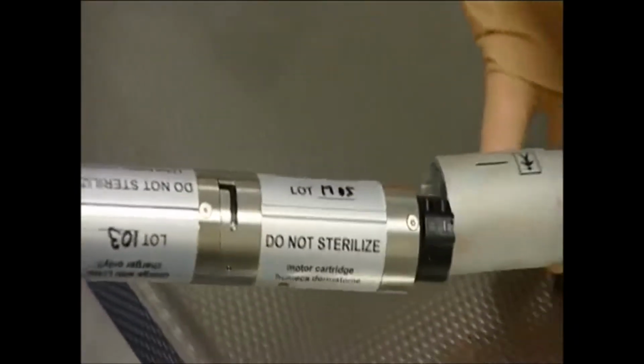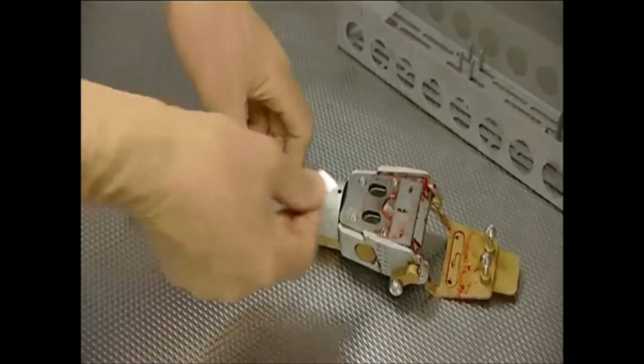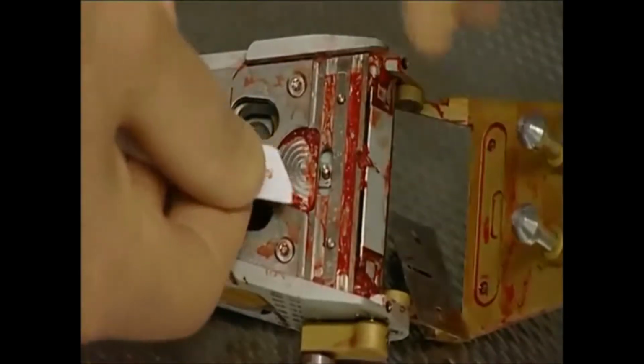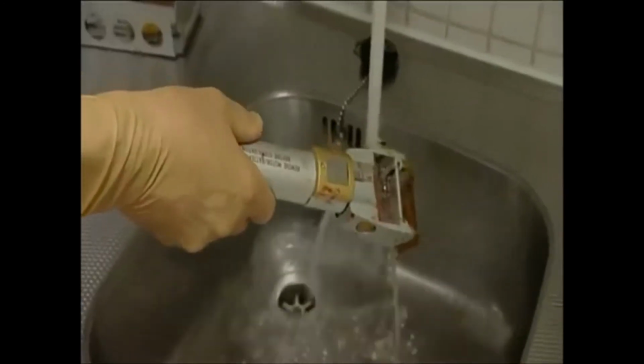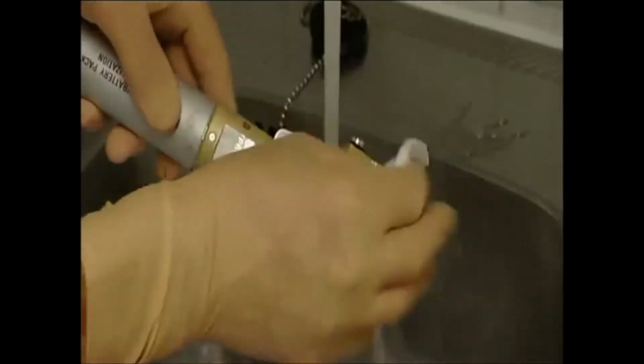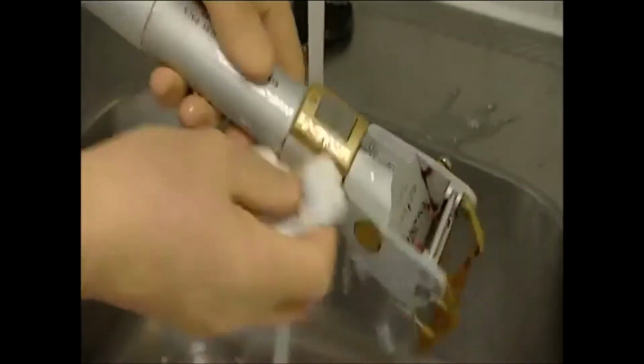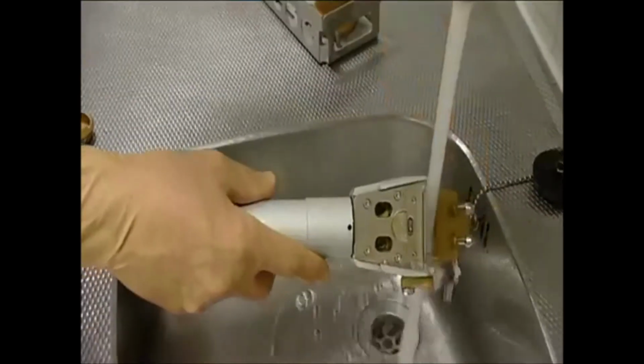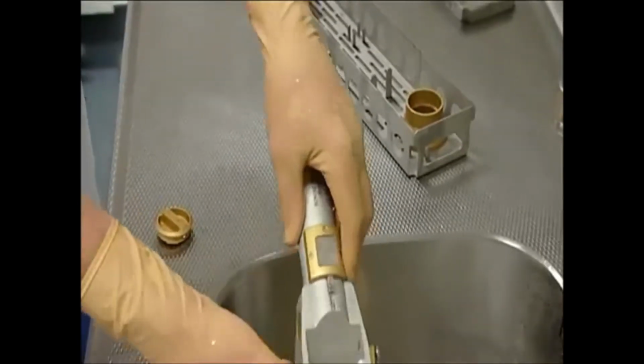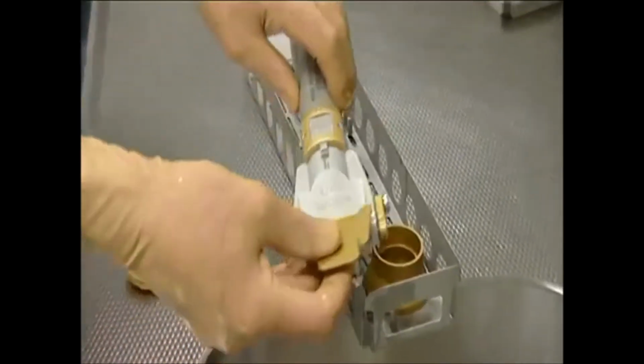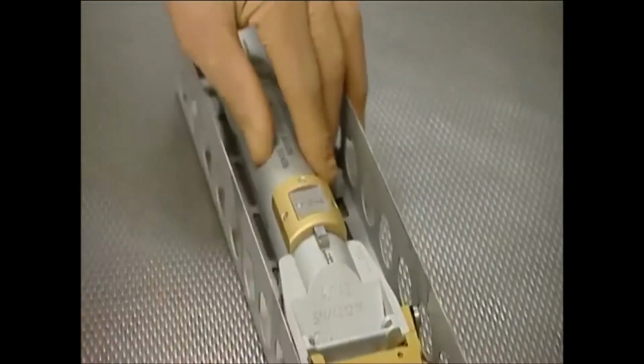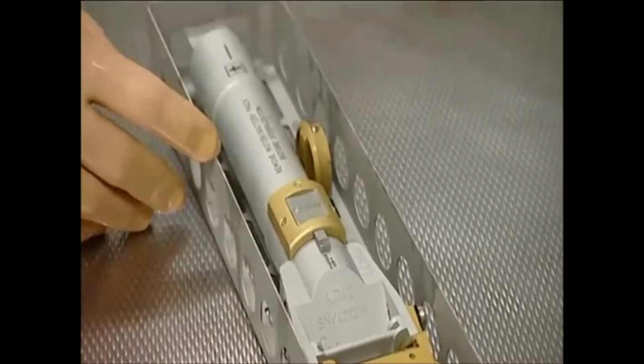After use, when motor and battery have been taken out, the blade is removed from the instrument. It's recommended to remove blood and tissue remnants shortly after use by rinsing with warm water and a soft brush or gauze. This pre-cleaning will prevent unnecessary corrosion of the instrument. For washing and sterilizing, the dermatome is placed in an autoclave case that can only hold the instrument after removal of motor and battery, thus preventing accidental sterilization of these parts.